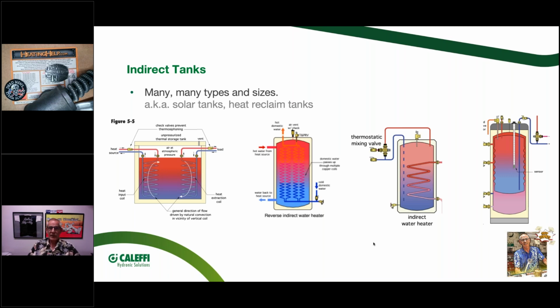It could also be used as a buffer tank. You could put boiler input into that tank and use the water for going to a micro load, for example, so you're not short cycling your boiler. So it's really just a heat exchanger. Just because it says indirect water heater on it doesn't necessarily mean it has to be used for domestic water.